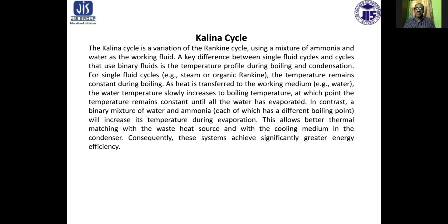A key difference between single fluid cycles and cycles that use binary fluids is the temperature profile during boiling and condensation. For a single fluid cycle, for example steam or an organic cycle, the temperature remains constant during boiling. As heat is transferred to the working medium, that is water, the water temperature slowly increases to the boiling temperature, at which point the temperature remains constant until all the water has evaporated. In contrast, a binary mixture of water and ammonia, each of which has a different boiling point, increases its temperature during evaporation. This allows better thermal matching with the waste heat source and with the cooling medium in the condenser. Consequently, this system achieves significantly greater energy efficiency.